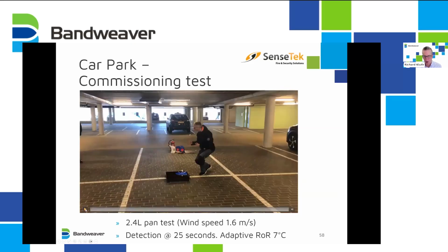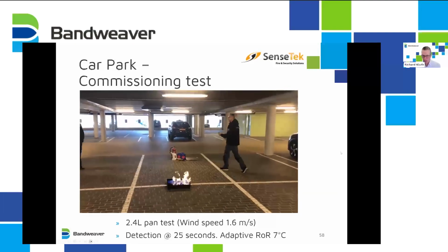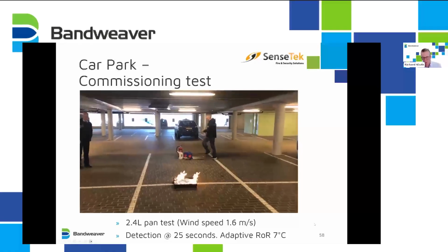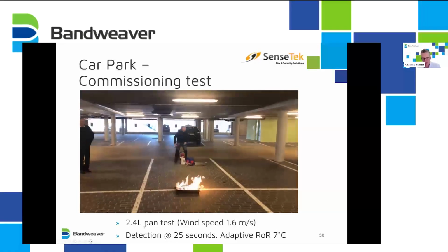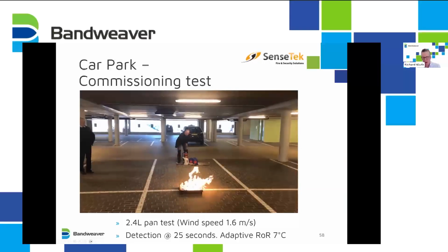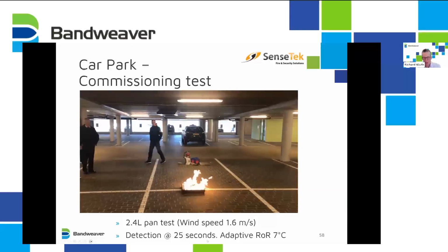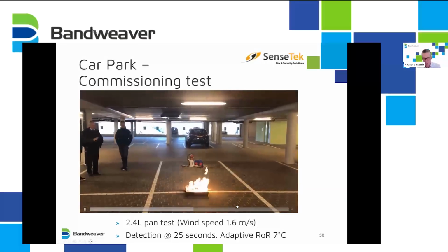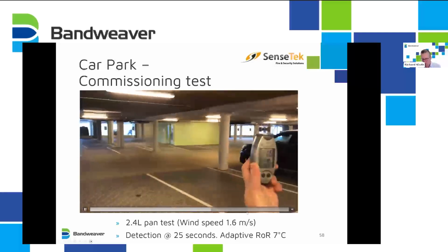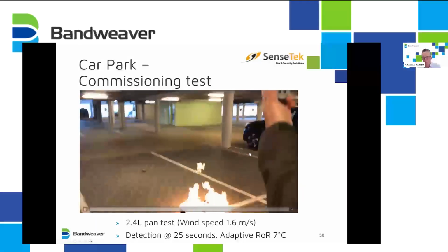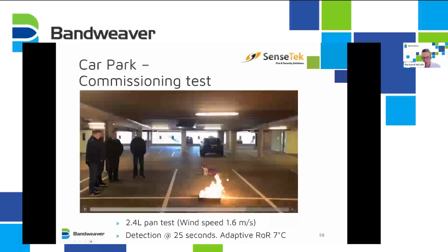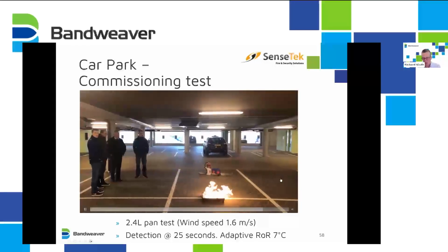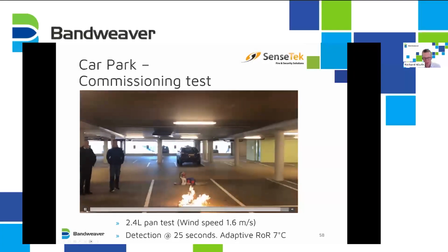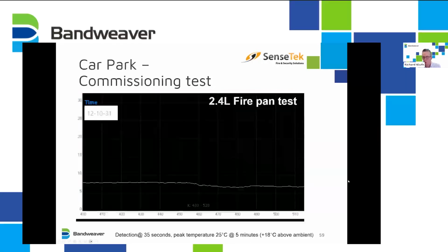So if we look at our partner SenseTek lighting the fire, in this case the wind speed was above 1.6 meters, so it was a 2.4 liter, and the detection was around about 25 seconds in this scenario. You can see they're varying from 1.3 up to 1.8, and you can see the detection there happens within 25 seconds. We have some data here where, because the system gets data, we've taken a trace.